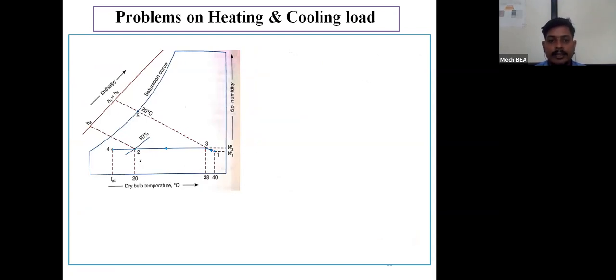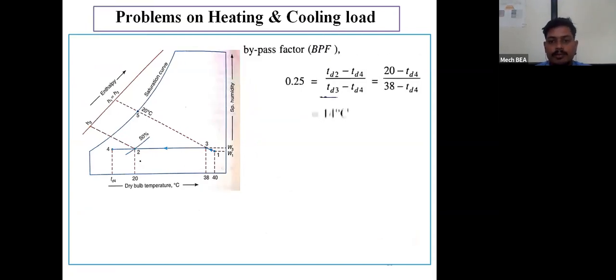And to find out the exact value, I am going to use the bypass factor formula. The bypass factor will be given by the equation TD2 minus TD4 divided by TD3 minus TD4. So here I will get the value of TD4, that is nothing but the surface temperature of cooling coil, as 14 degrees centigrade. After getting this exact value, locate point number 4 on the psychrometric chart.